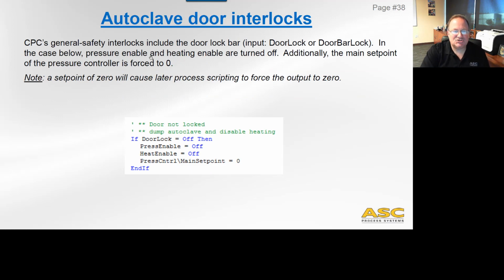Autoclave door interlocks. Okay, CPC's general safety interlocks include the door bar lock. As an input, it might be called door lock or door bar lock. In the case below, pressure enable and heat enable are turned off. Additionally, the main set point of the pressure controller is forced to zero. And so this is a pretty simple thing. By setting the pressure control main set point to zero, far down below this general safety interlock in the actual pressure logic controls, there will be a condition which says if pressure control main set point equals zero, then force the output to be zero. So you don't have to set the output to zero here, because just by the fact that this is above the other logic, it will generate the correct logic condition in the pressure section of the script.